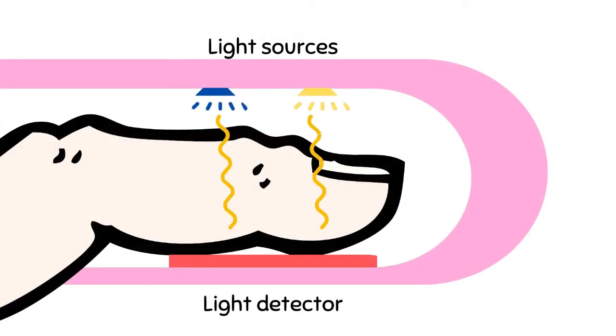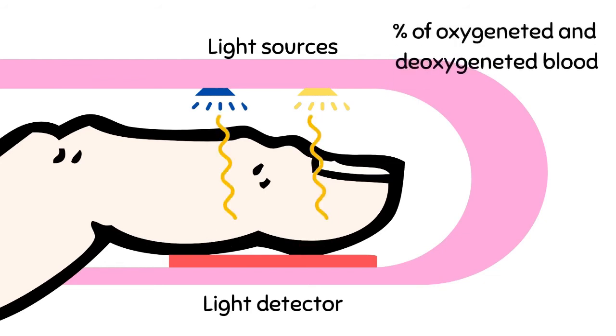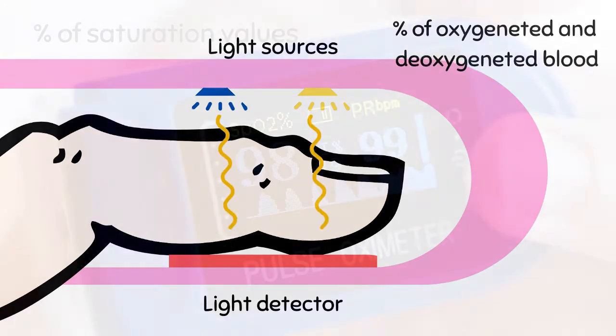When this is put around the finger, the two lights of 650 and 950 nanometers pass through our tissues and measure the amount of light that reaches the detector. The measurement is converted by the tiny chip to the corresponding percentages of oxygenated and deoxygenated blood.